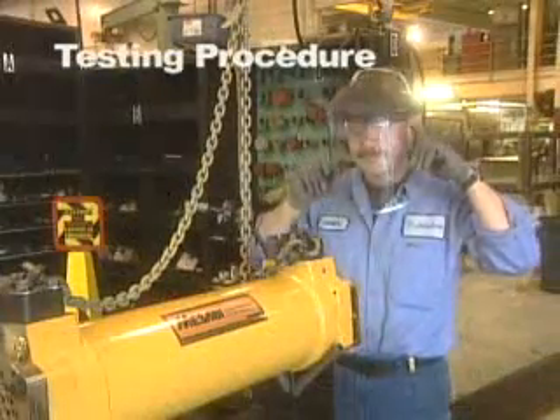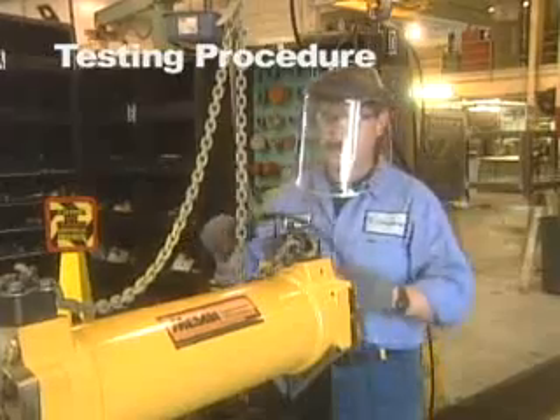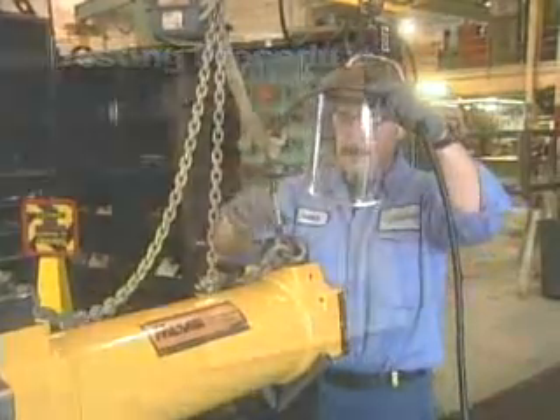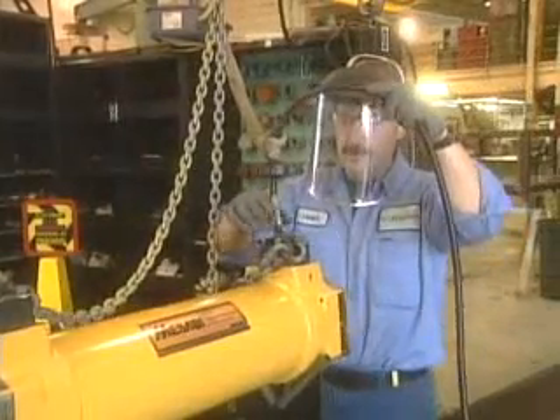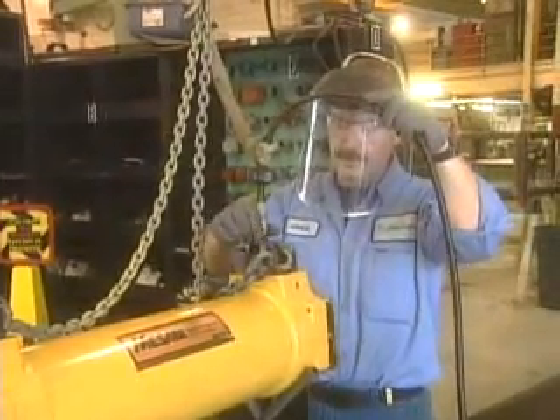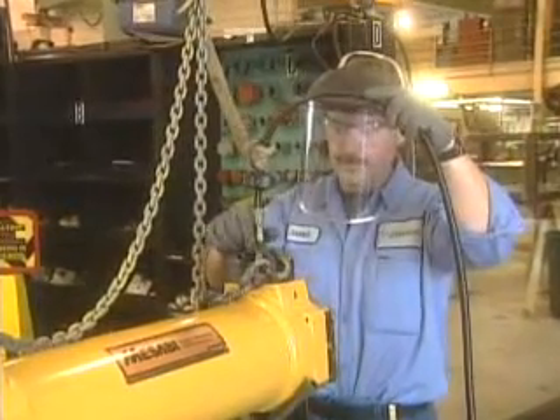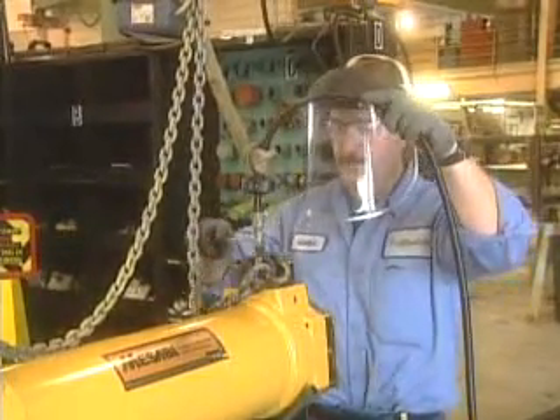Because testing requires pressurizing the system protector, full face protection must be worn. To test the shell side, typically the oil side, follow the pressure cycle steps in the System Protector Service Manual. Only use fittings appropriate for the test procedure and apply pressure slowly. If a leak is detected, pressure should be released prior to repair.